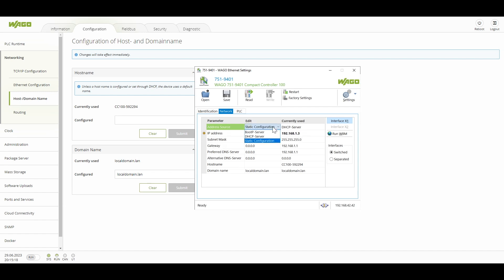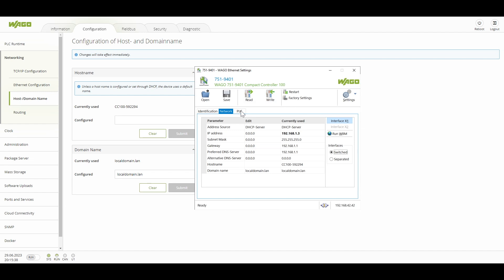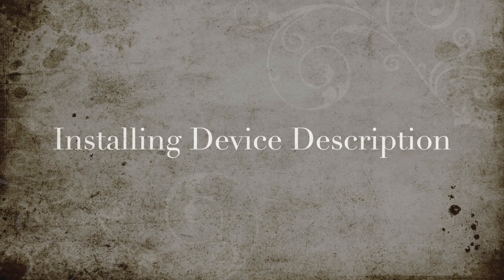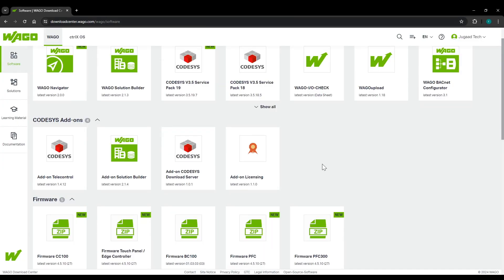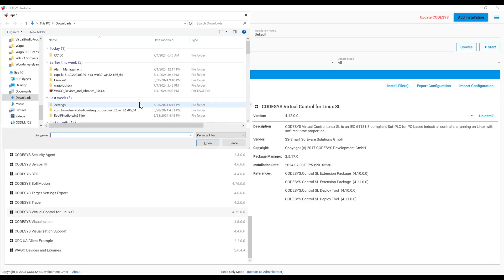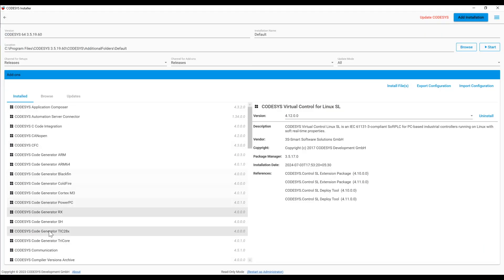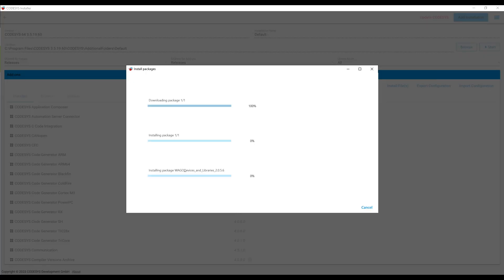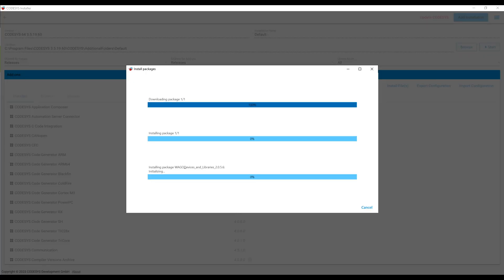Using the WAGO Ethernet Setting software, we can select and configure the IP, switched or separated mode, and everything else on the configuration side. We can read and write all the configuration using this software. Now let's go and install the device description. In Codesys, we need to install the device description — we download it from the Download Center and then use the Codesys installer to install it. We select the install file, load the package, and it will install into the Codesys IDE.